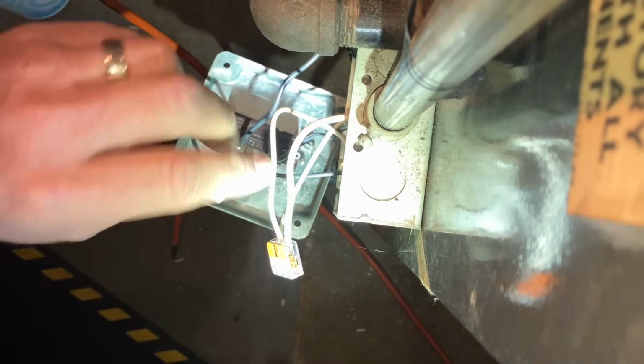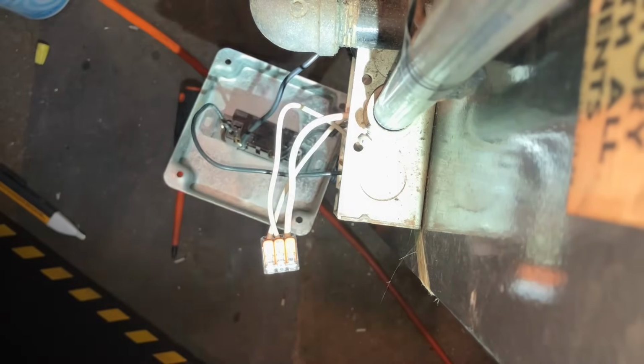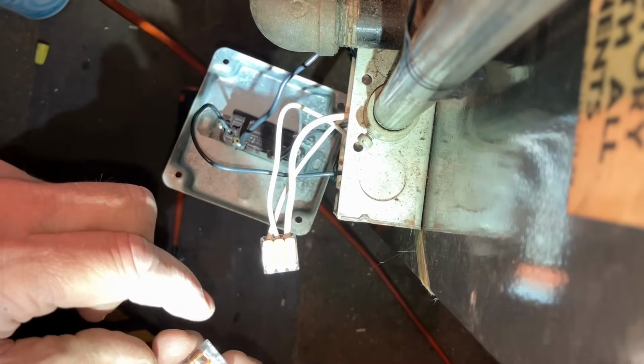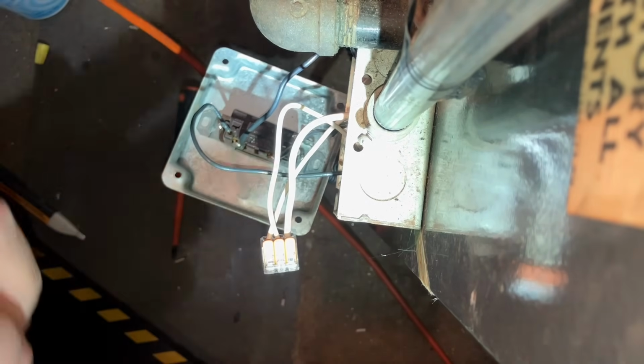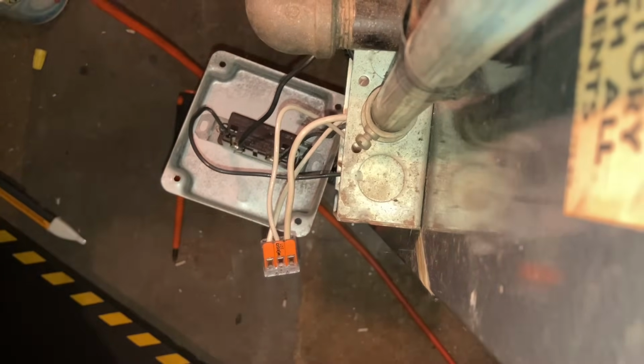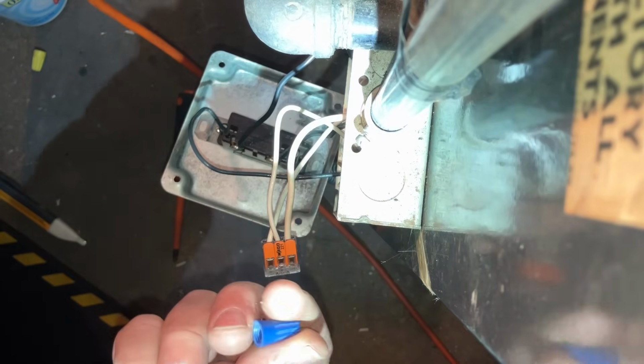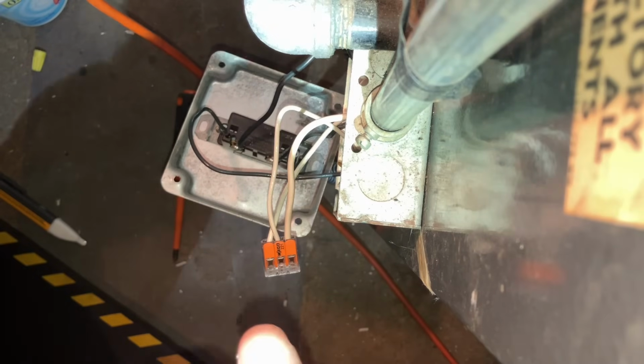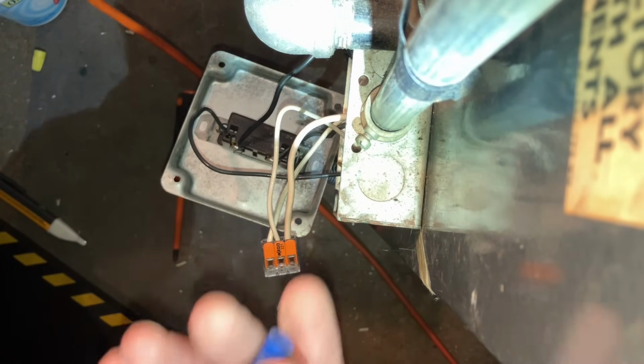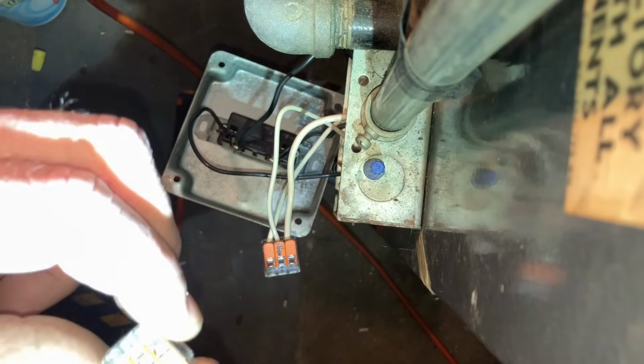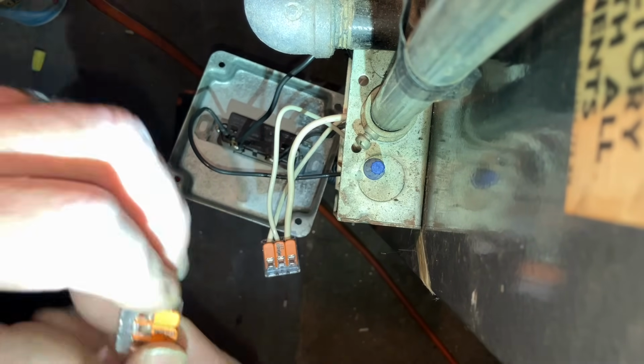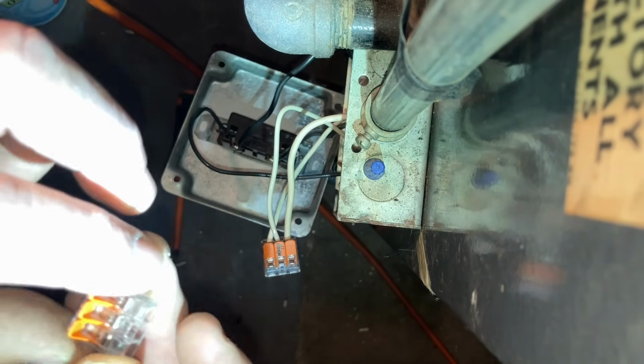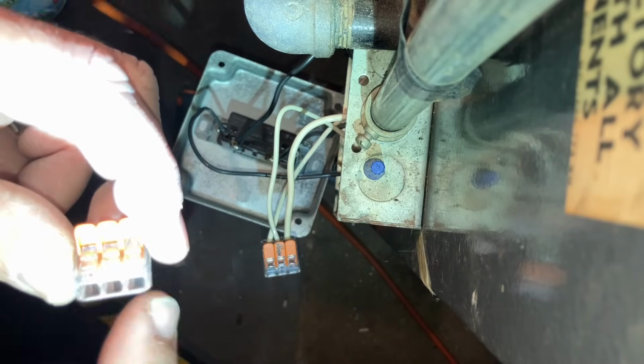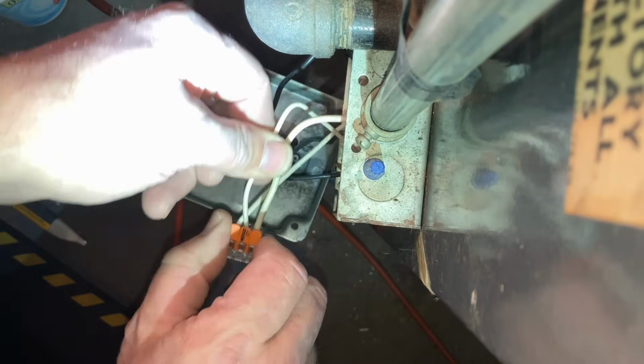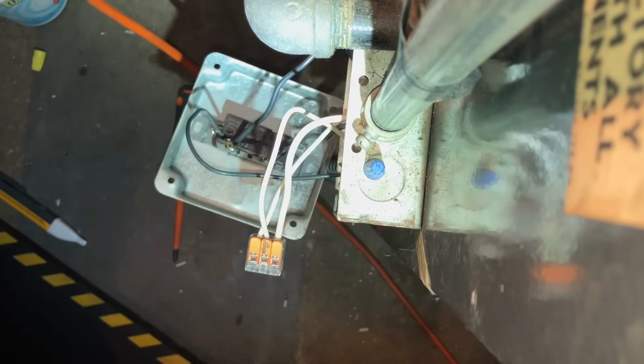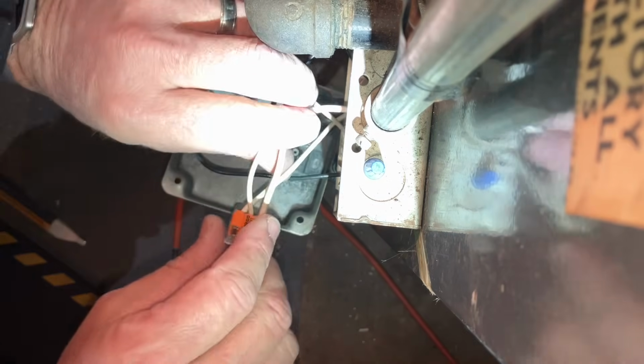Oh, I've never seen one of those. Okay. This is called a lever connector by Wago. It's a European brand, but you'd appreciate this. This is a traditional wire nut for a certain gauge of wire, right? It technically should only be used once. This is a Wago, the model 221 lever connector, and it has these levers, and this one is for 3 conductors. For certain gauges, right? You put the wires in there, you push them in, you go like this, and guess what? They are not coming out, and they're reusable. Pretty cool, huh? That's for a range of gauges.